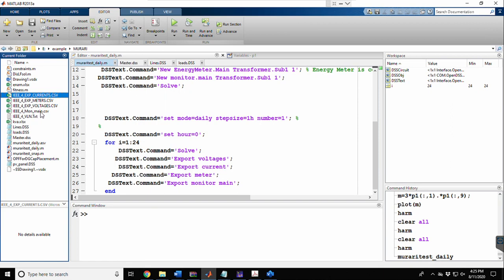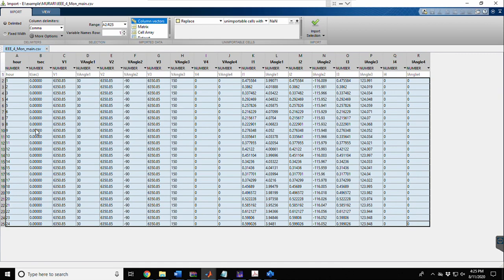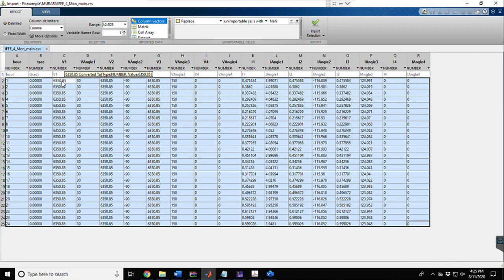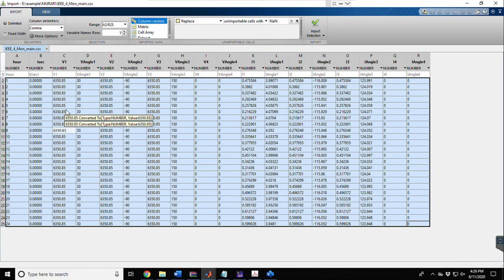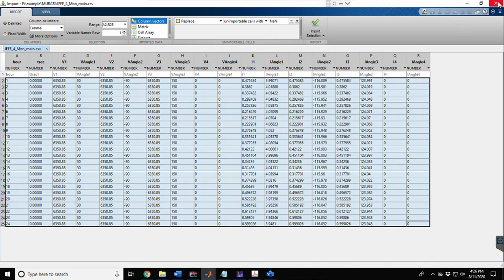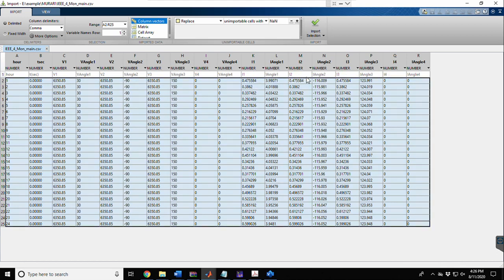Now looking at the monitor export file: since we ran the load flow for 24 hours, we have 24 voltage readings at the transformer primary side. Since the monitor is placed at the primary source side, the voltage magnitude does not change with time. However, for current, the values for phase 1 vary with respect to time. The network is balanced, so all phases have the same current magnitude at all times, but displaced by 120 degrees.